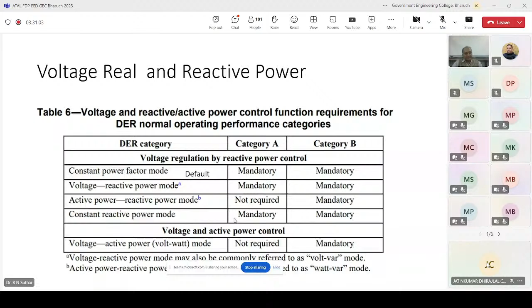When you have a voltage reactive power mode, your voltage and reactive power should remain fixed. When you have an active reactive power mode, there should be a certain relationship which will be given by the grid code. This is the relation of active and reactive power which has to be followed by you when you are connecting the RES to the grid. So for a 1% variation or 10% variation of active power, your reactive power should vary 2% or 1%, and accordingly you have to make the changes. And in constant reactive power mode, irrespective of change in active power, your DER should be able to provide the constant reactive power. So these are the different modes in which your DER should operate while connected to the grid.